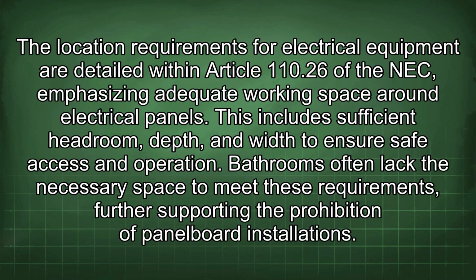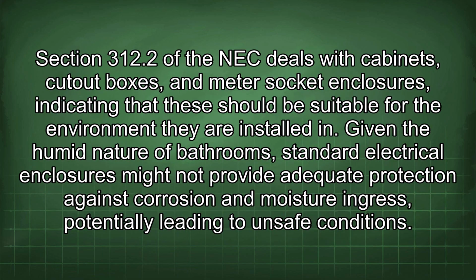The location requirements for electrical equipment are detailed within Article 110.26 of the NEC, emphasizing adequate working space around electrical panels. This includes sufficient headroom, depth, and width to ensure safe access and operation. Bathrooms often lack the necessary space to meet these requirements, further supporting the prohibition of panelboard installations. Section 312.2 of the NEC deals with cabinets, cutout boxes, and meter socket enclosures, indicating that these should be suitable for the environment they are installed in.